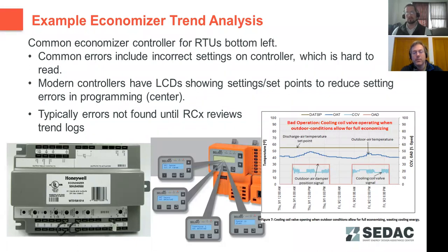The other way you could do compliance with the economizer fault detection and diagnostics is through BAS trend data. A lot of BASs have the capability to report back to an operator, using logic that's programmed into them, whether there's an error with the system. In this case, in the image, it's indicating that it's cool enough outside to do free cooling with the damper fully open, but the damper is not opening enough and the cooling valve is coming on, or some error such as that. And so it's going to report back that there's a problem. There's adequate cooling capability with the outside air alone, but the cooling valve is still opening for some reason.